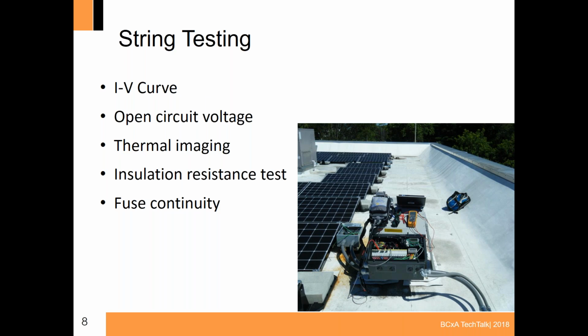The next one down, the open circuit voltage. Again, that's basically just taking a voltage reading. Every module, on average, is going to produce about 40, 50 volts DC. We string them together in series, and Engineering 101 tells us that voltage in series adds. So we have a very good idea what that expected voltage should be. So we basically verify that. We test every single string to make sure that we get right in that range, and we flag any voltages that are out of that range. So we want to make sure that they match properly, and like I said, we flag anything that's not.